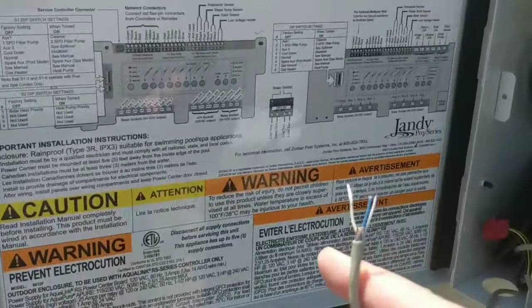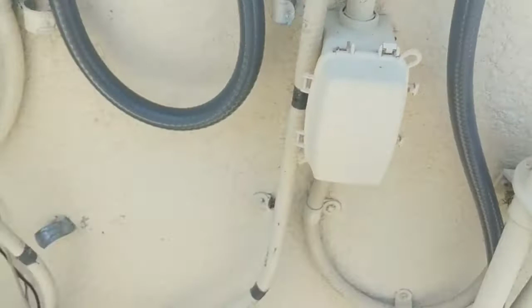From my 60 amp switch I took 6 gauge wire, plus a ground. The ground is already on the board. My 2 lines run all the way through and into the heater, wired in there. You can see the 2 6-gauge wires there, so I've got 6 gauge all the way for this board.